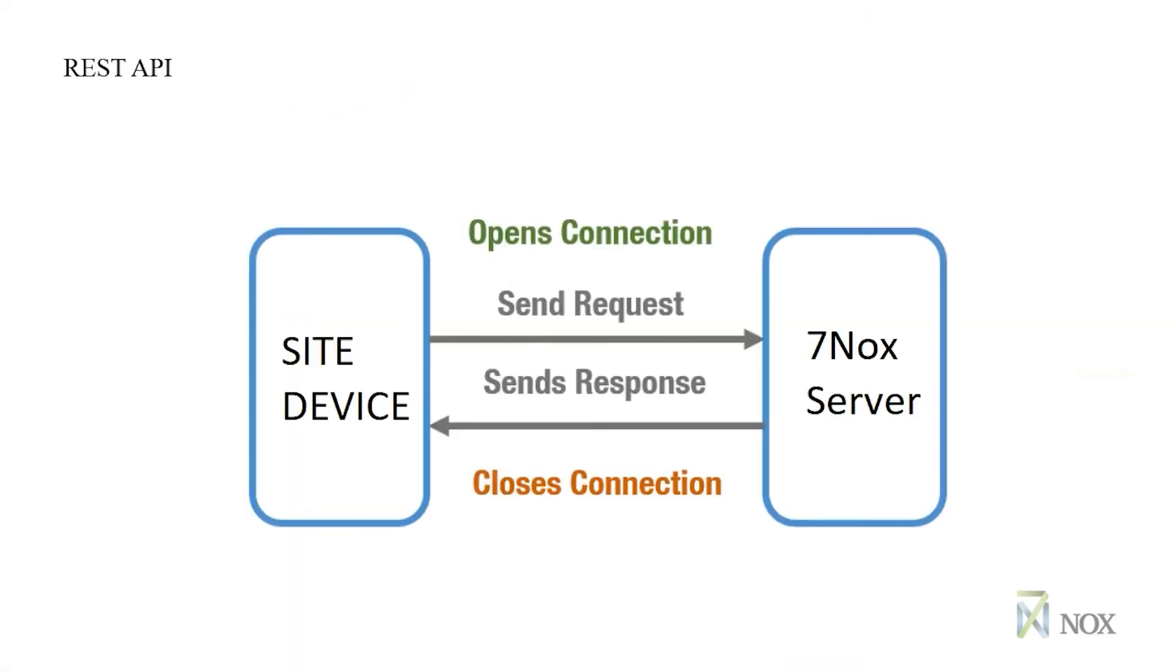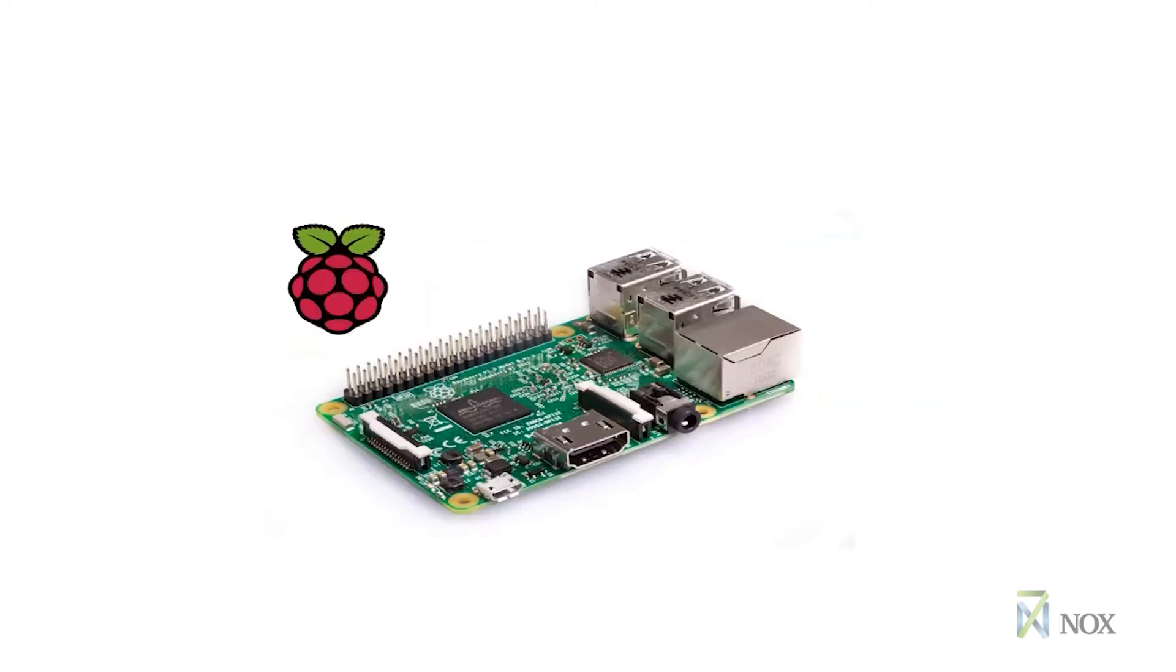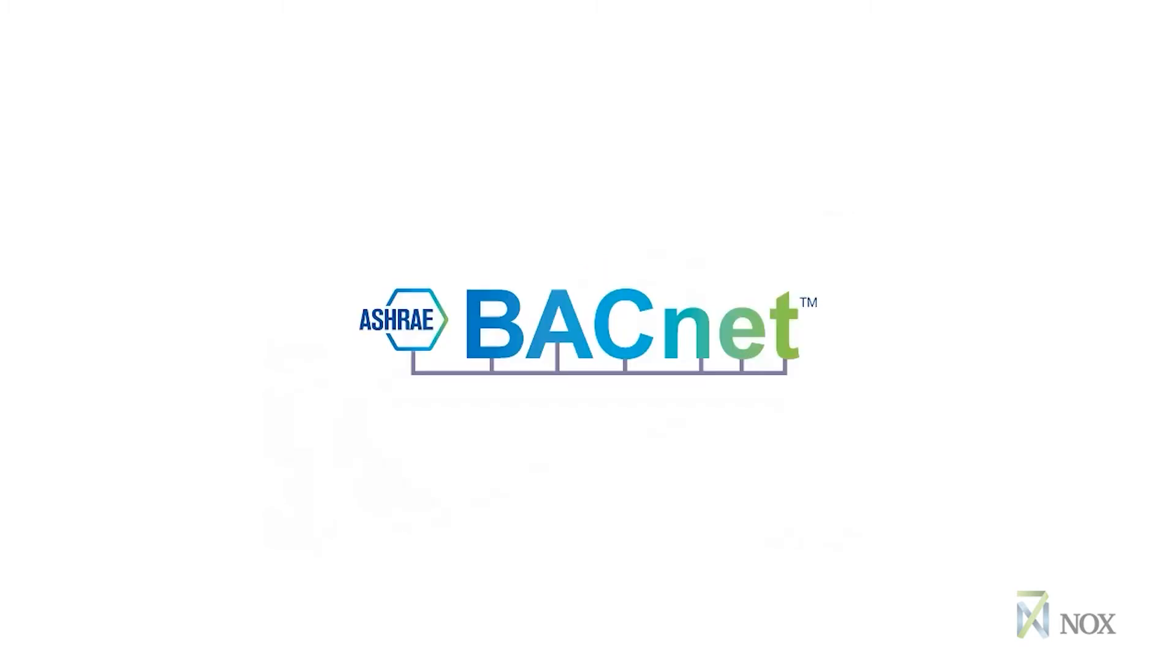7NOX utilizes REST API technology to communicate between the SITE and the cloud services. The 7NOX SITE device is a small embedded Linux computer running the 7NOX client application. The client application requires very low resources to operate, so it can be deployed on a device like a Raspberry Pi or equivalent. The client application is a BACnet device which can be discovered by any BACnet control system.